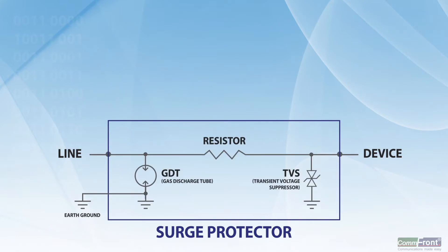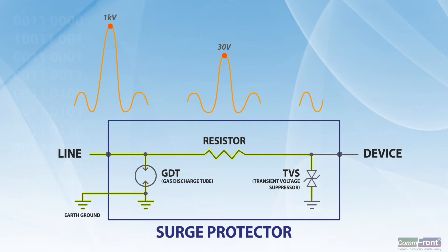Surge protectors often come with three stages of surge protection: gas discharge tubes (GDT), protection resistors, and transient voltage suppressors (TVS). When a high voltage surge is introduced into the input, the GDT conducts electrical current after becoming ionized, which in turn discharges the high voltage surge to the earth ground. The excessive voltage will be further clamped to a safe range that the equipment can accept by the TVS.